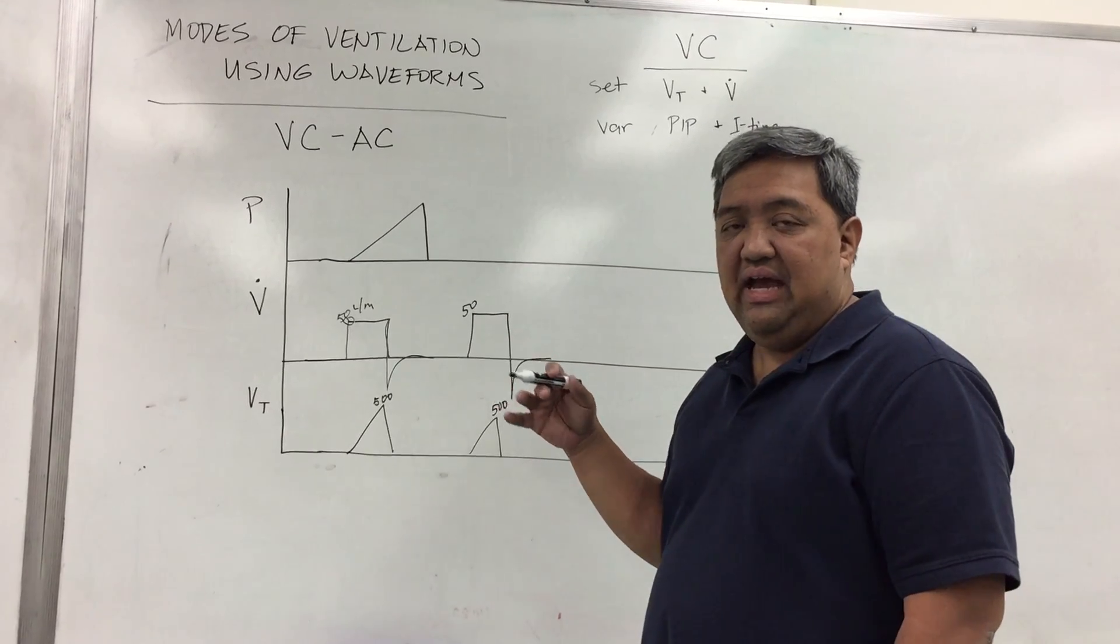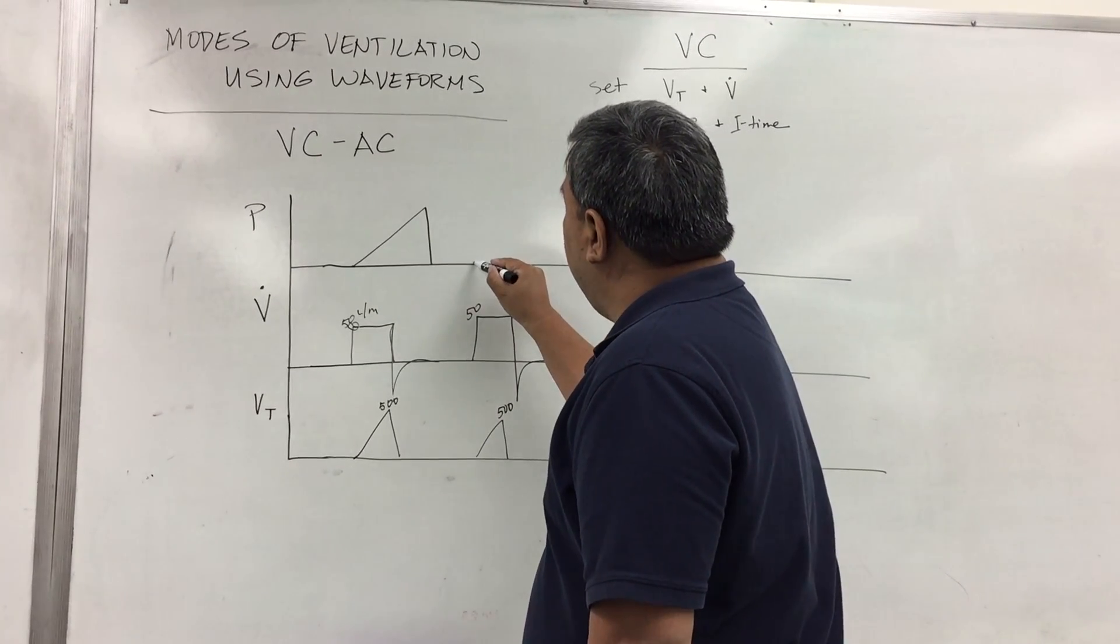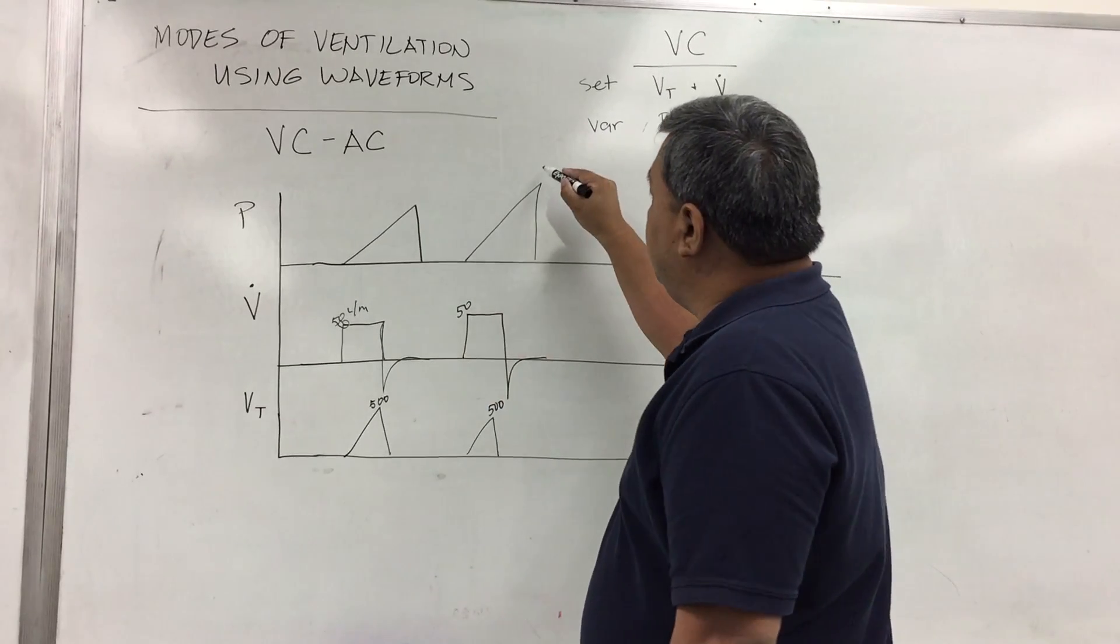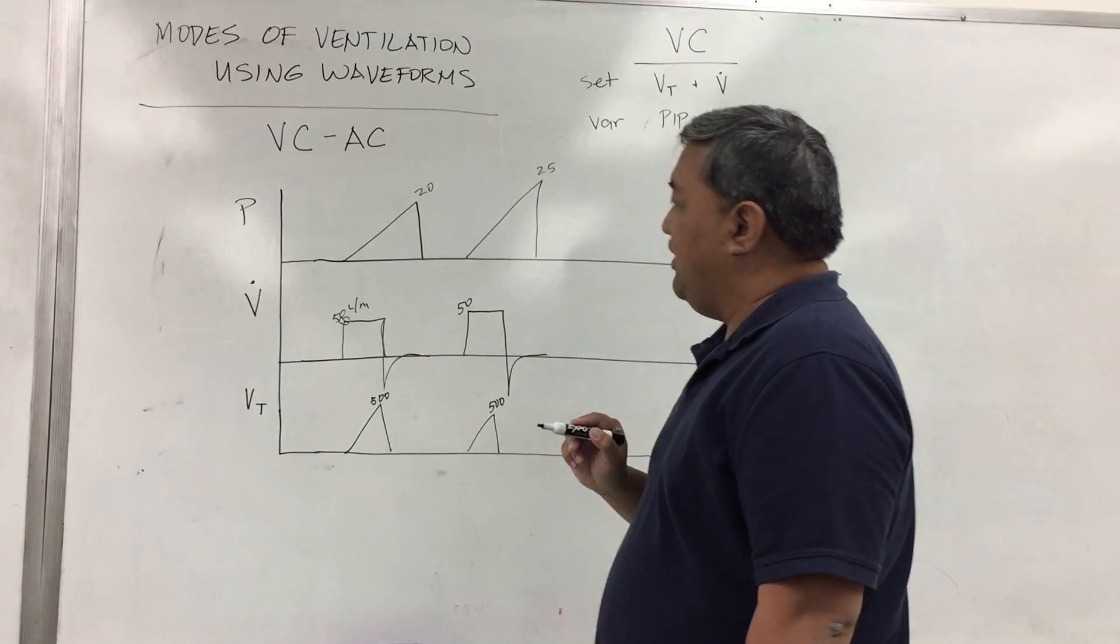However, if the next breath has some sort of resistance or compliance problem, then most likely your pressure may be a little bit higher. In this case, let's say this is 25 and let's say the earlier breath is 20.